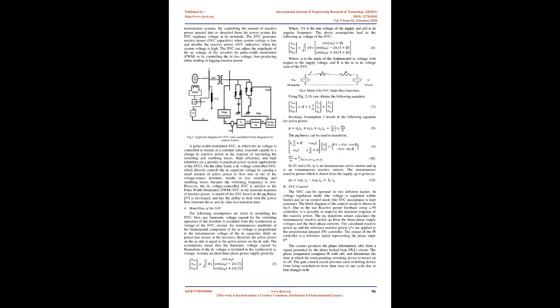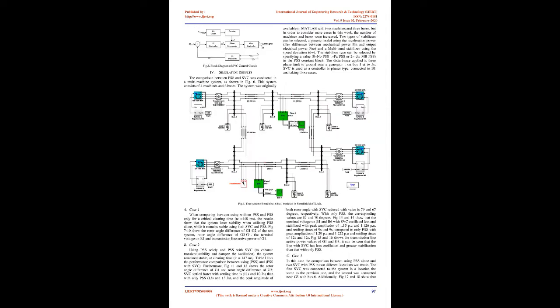signal. This filter introduces a phase lag at lower frequencies, which has a destabilizing effect on the exciter mode, thus imposing a maximum limit on the allowable stabilizer gain. In several cases, this is often restrictive and limits the overall effectiveness of the stabilizer in damping system oscillations. In addition, the stabilizer has to be custom designed for each type of generating unit depending on its torsional characteristics. B.